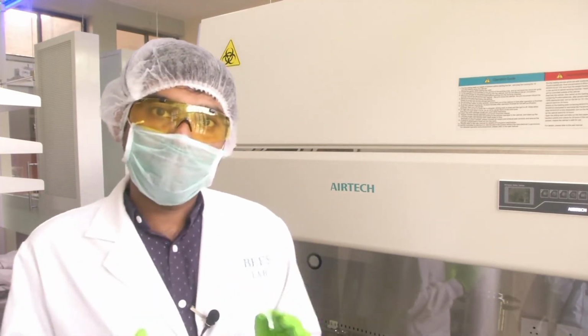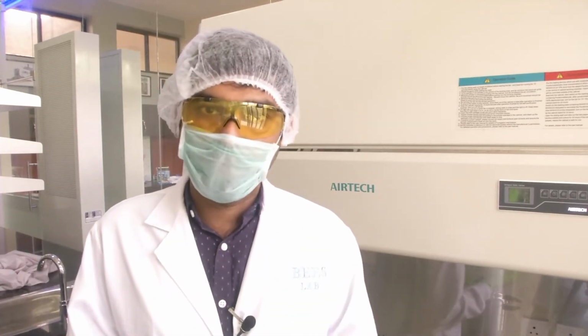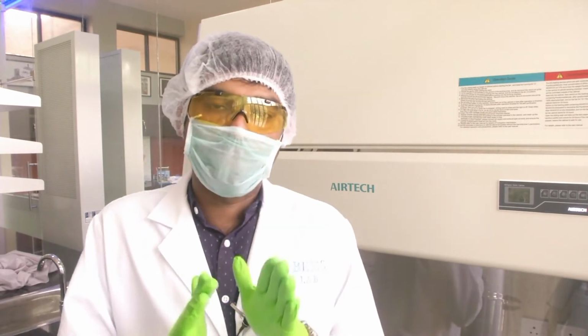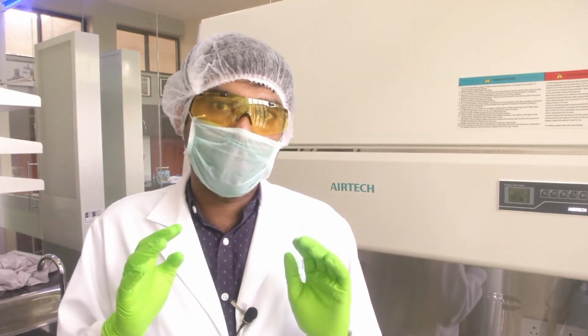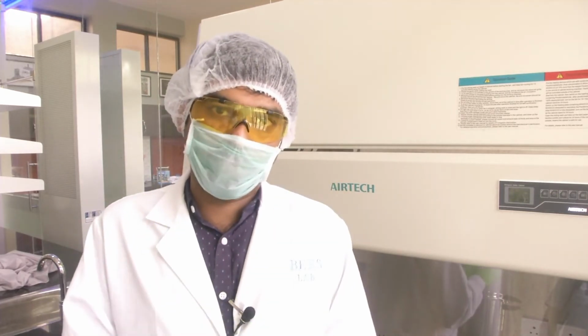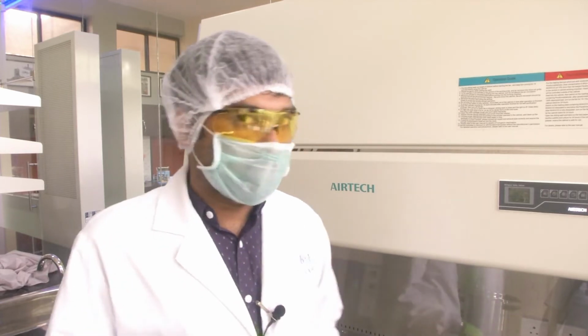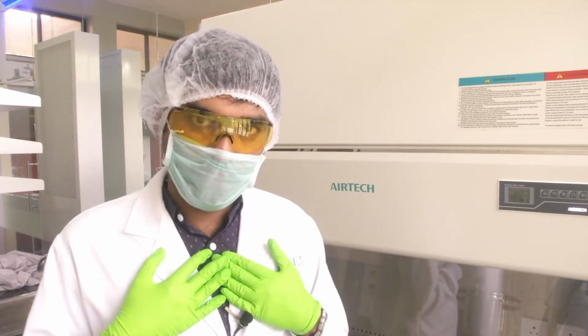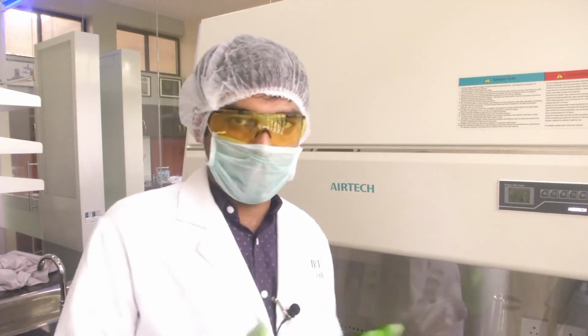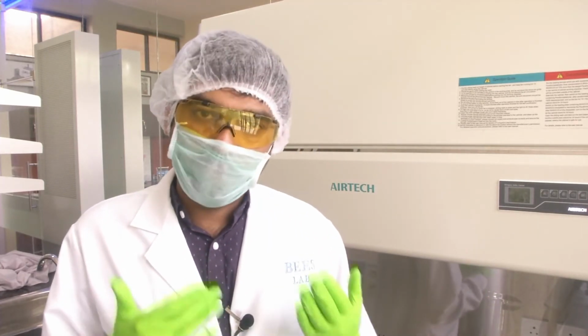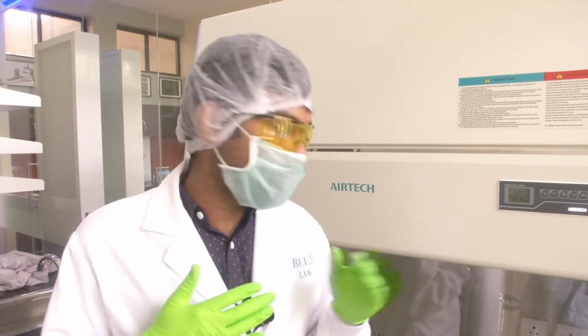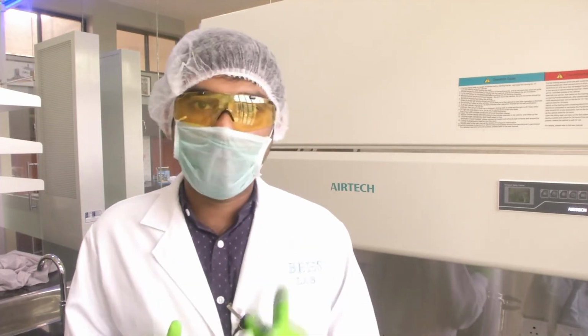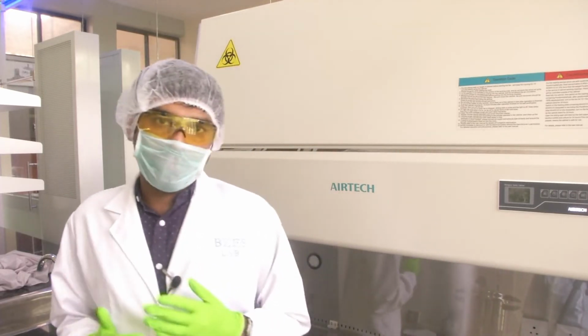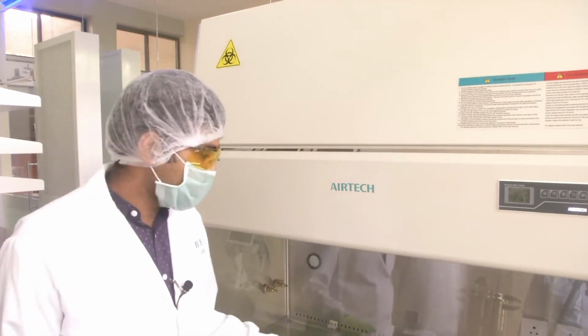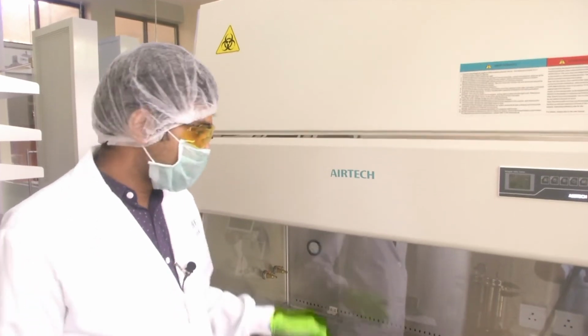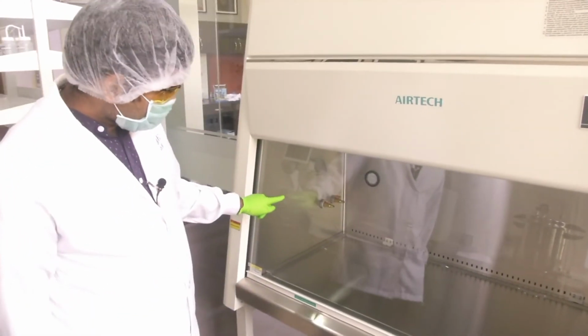If it is something that we have introduced and we want that sample to change, that is different. But suppose the environment itself is making the sample change in a way that we do not desire, then that product is not protected, but we need to protect the product from it. So that is called product protection. So 3 main protections are there: personal protection, environmental protection and product protection. Okay. A class 1 biosafety cabinet basically provides personal protection and environmental protection. Product protection is not provided. What it means is about the air that is used. In this cabinet you can see there is an enclosed area inside, right. If you look inside, there are 2 nozzles.